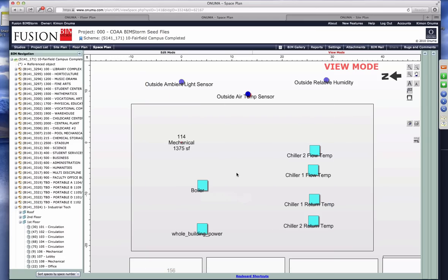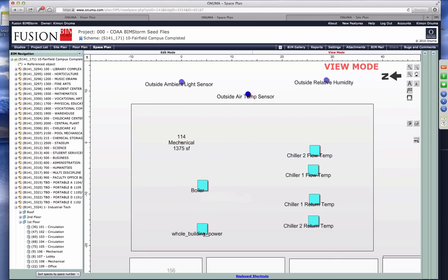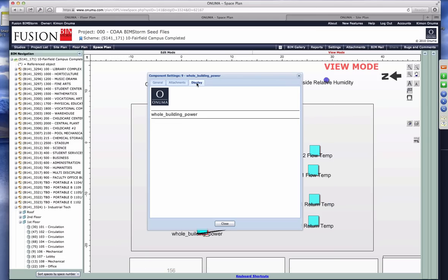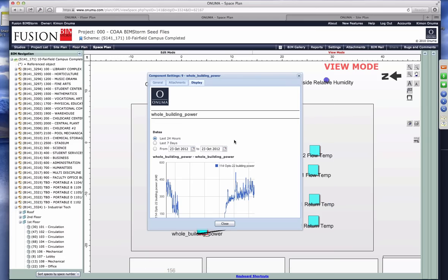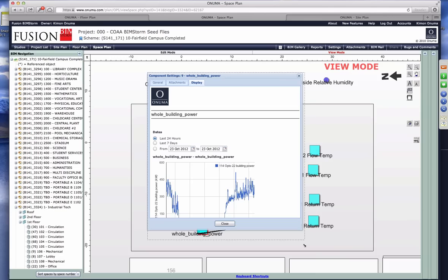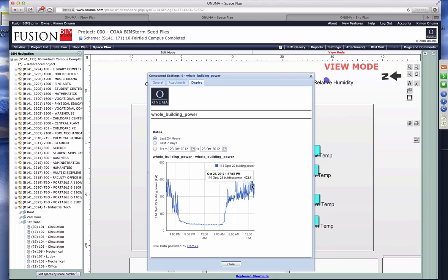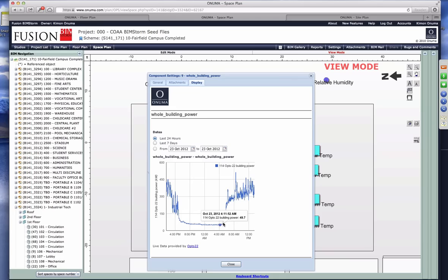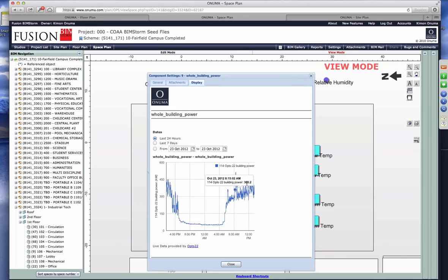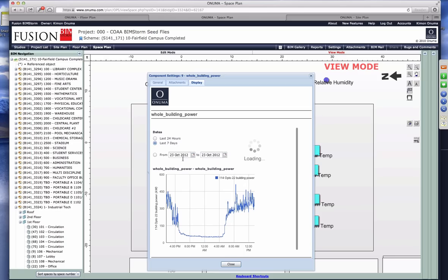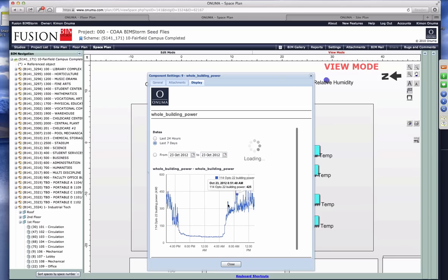That's the outside air temperature. Then if we go into the whole building power, I know that Andreas yesterday when we had a conversation with Balfour Beatty, we were trying to figure out if there's anything in these buildings that would give us information about how the building is performing. This is the one building that we have sensors attached to it. This one shows whole building power usage and you could see middle of the night there's not much power use, and as morning kicks in everything starts powering up. You see a minute-by-minute chart here for the last 24 hours or the last seven days. You can start seeing a pattern going on here as well.